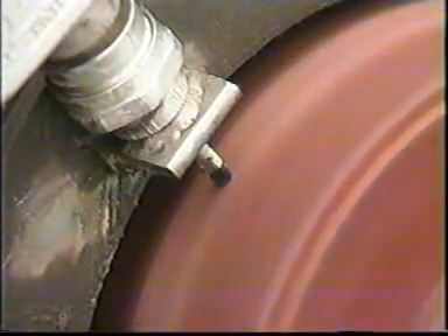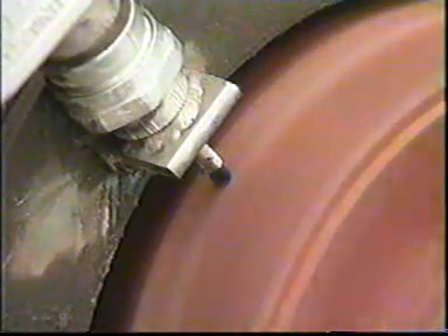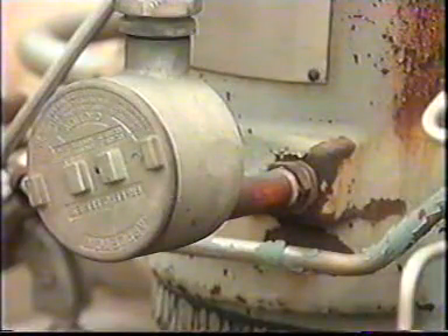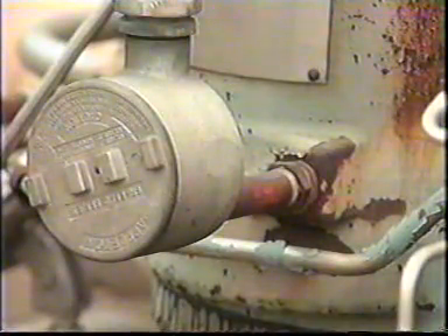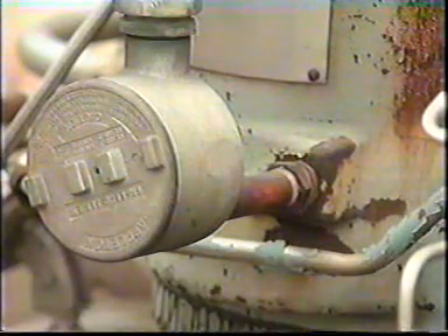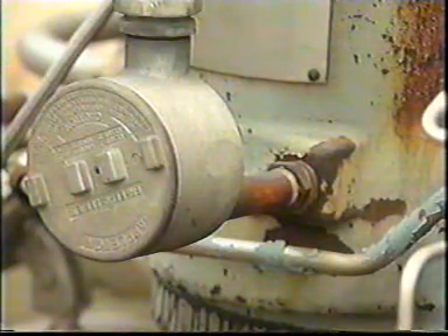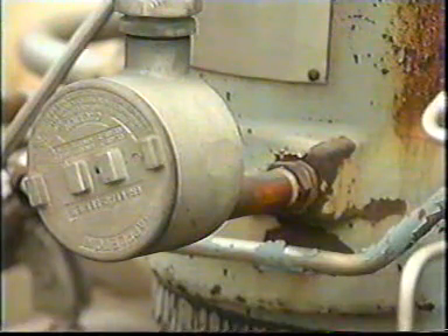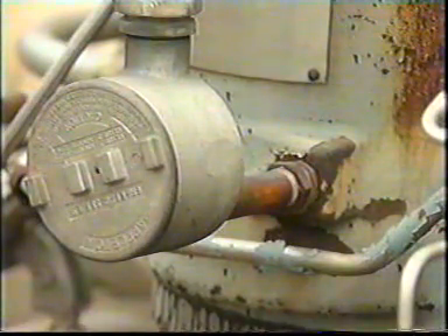Radial measurements are perpendicular to the axis of rotation. A radial-mounted proximity probe measures shaft position relative to the casing or bearing. Axial measurements are parallel to the rotational axis. An axial-mounted proximity probe can show the shaft or thrust position between shaft and casing.